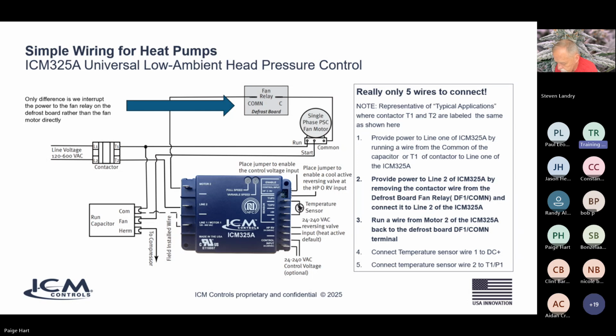So in this case, you have the 3 wires up at the top, you have the 2 wires for the sensor, and you have an additional 2 wires for the reversing valve. So this one would be a 7-wire application: 5 wires for the standard wiring and 7 wires for this product with the heat pump.